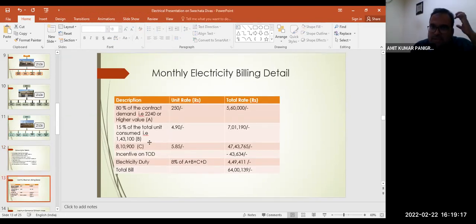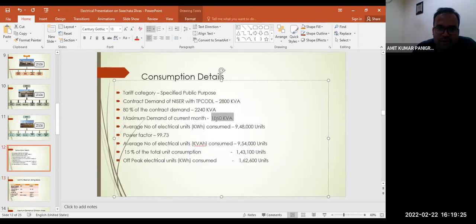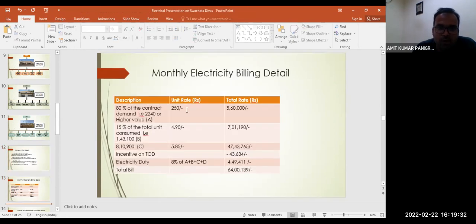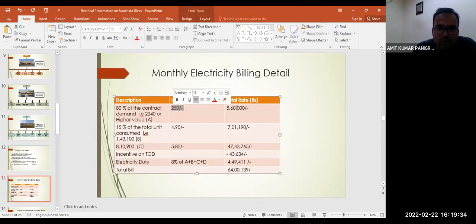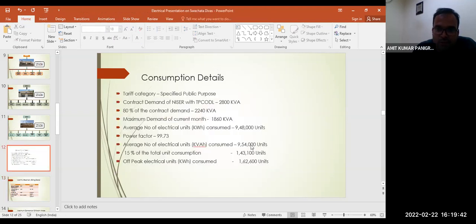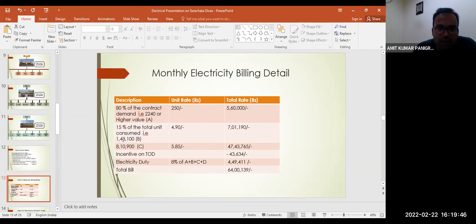So what are the major components of the electricity billing? First is the 80% of the contract demand. As we have only used 1860 kVA in the month, we have to pay for 2240 kVA. The kVA charge is 250 rupees, so the demand charges come to around 5,60,000. And then 15% of the total unit. The total unit is 9,54,000, and 15% of it is 1,43,000.